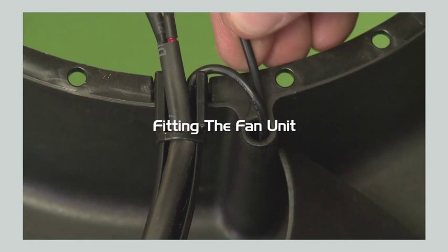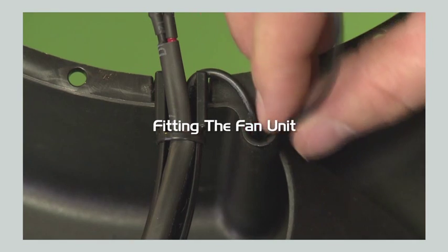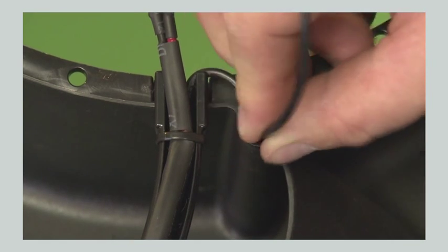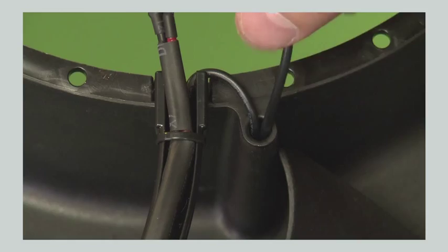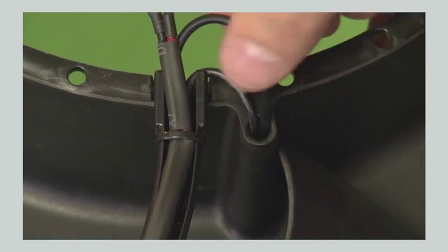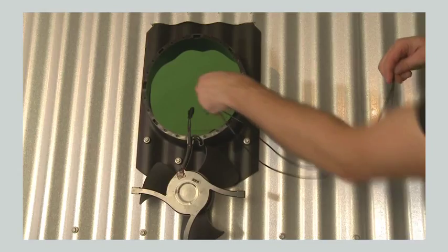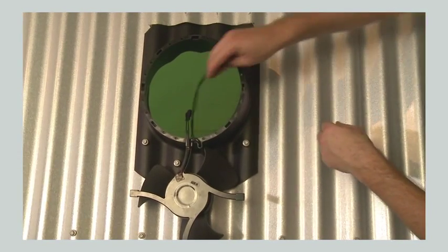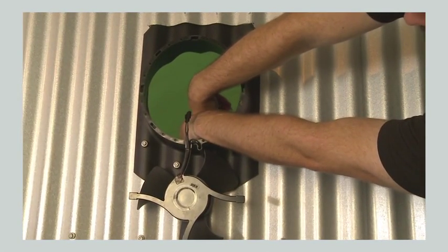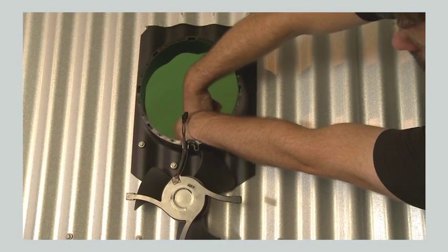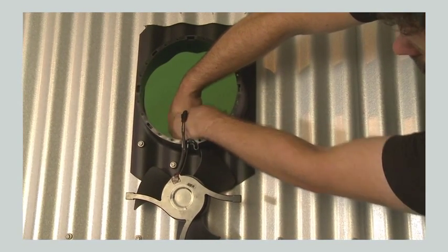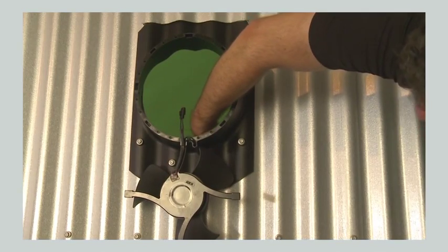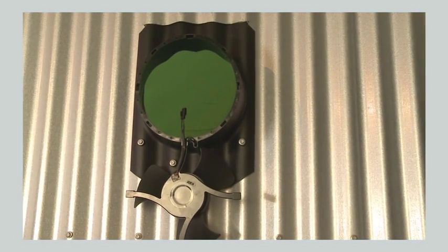With the fan removed pass the two wires with the terminals individually through the conduit in the base. Reaching in through the hole in the base either join the two terminals together if you wish to bypass the thermostat or connect the thermostat to the terminals. Hang the thermostat within the roof cavity making sure that it does not rest directly against the ceiling or insulation. You can shorten the drop if necessary by looping the wires. Do not cut and join the wires as this may affect the unit's efficiency.